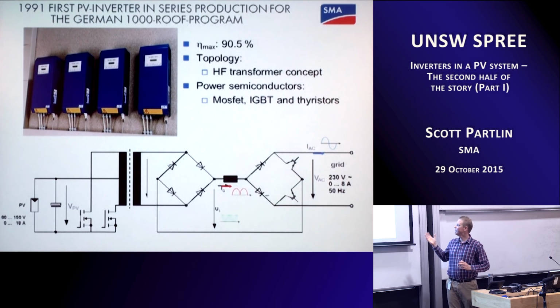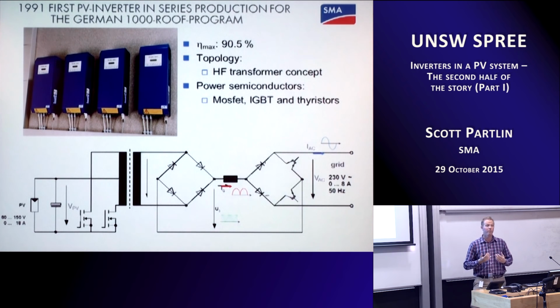This is the first mass-produced PV inverter anywhere in the world. It had a maximum power output of about 700 watts. It was a transformer-based inverter with a high-frequency switching transformer, and you've got a picture of the circuit diagram there. One important point for an inverter: back then it had 90% efficiency, obviously a long way off the ideal 100%. That was back in 1991.